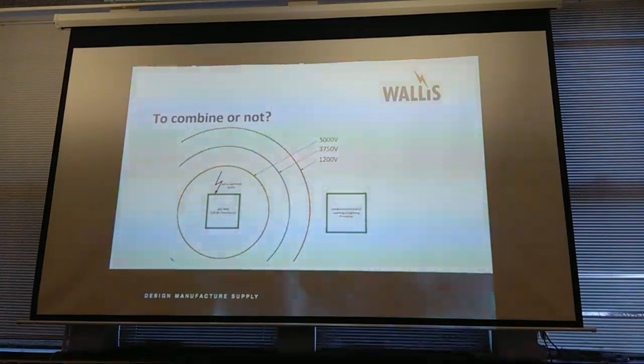Yeah, so what this is trying to demonstrate is that the 11 kV RMU close coupled substation, HV earth sitting around it, and then you've actually got your earth potential rise contours coming away. And to make that safe, you're actually trying to put the LV earth installation outside of that 1200 volt contour. Some of the old DNO standards give you a figure, and it says, shall be not less than 7 meters, shall be not less than 9 meters.